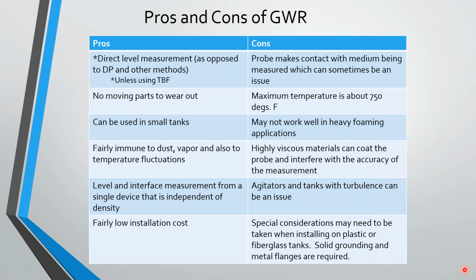Heavy foaming applications are always a problem, no matter whether you use this. However, one of the things I will say is that radar is much more forgiving of foam than ultrasonic. If any of you have used ultrasonic in the past, you will know that any kind of foam in ultrasonic simply didn't work well. Highly viscous materials can coat the probe and interfere with the accuracy of the measurement.